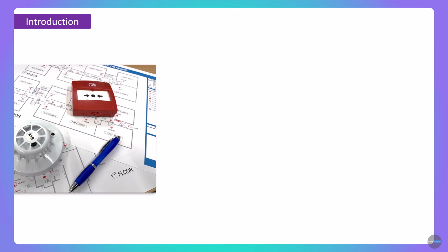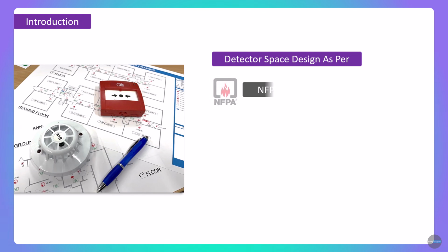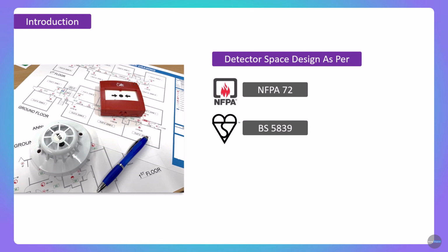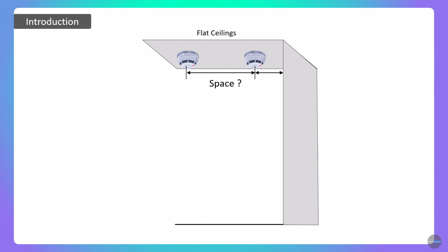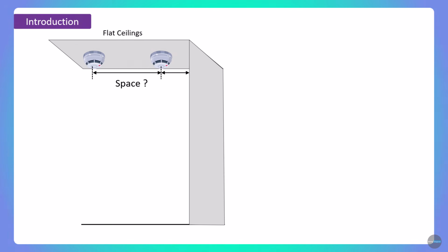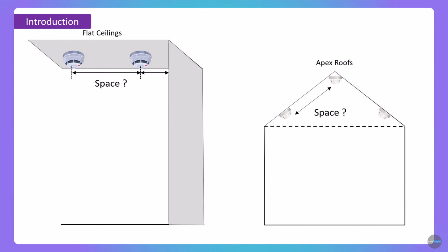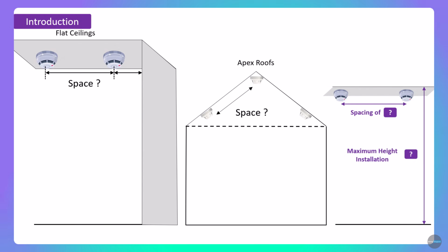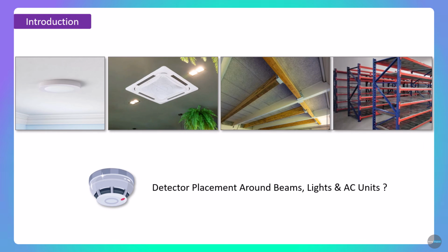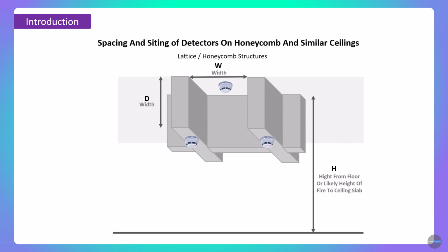Friends, the installation of detectors follows NFPA 72, British Standard BS 5839, and as per country standard code. Many people are unaware of these standards. In this video, we will learn about the standard spacing of detectors on flat ceilings, the spacing requirements for apex ceilings, the maximum installation height, and the correct placement of detectors around beams, lights, and AC units. We'll also understand the spacing and siting of detectors on honeycomb and similar ceilings.